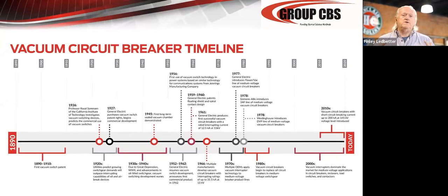If you buy these new medium voltage vacuum breakers and replace your old air magnetic breakers, you will not have to maintain them every year. You'll be able to extend your maintenance cycles out to 10 or 15 or 20 years, because the breaker is designed to operate for 20 years with a minimum amount of maintenance. The other good thing was that it's two-high stackable, so you can essentially get twice as many breakers in the same substation footprint that you have now. These were both very attractive alternatives.